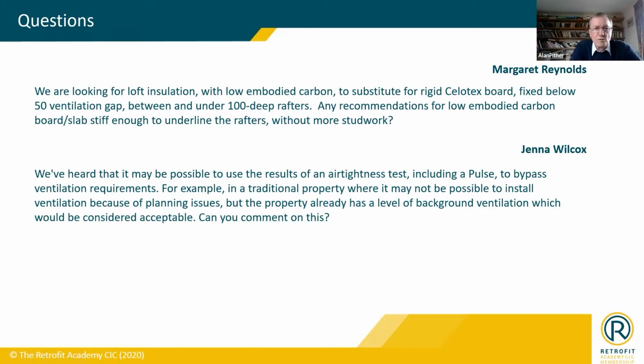We've had a similar question before, I think. I think the answer was it's not possible to avoid the need for installing fans with an air tightness test. You can confirm that you're okay with intermittent extract fans as opposed to continuous ventilation, i.e. that the air permeability is greater than 5, but you can't use it to confirm that you don't need any ventilation.